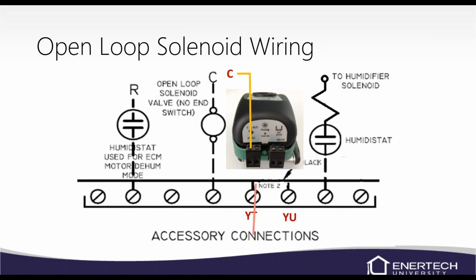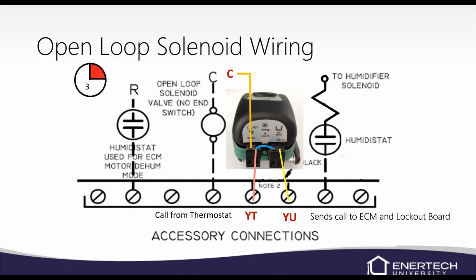Open loop solenoids, we have on our units the YT-YU connection that normally will have a jumper. If you're using one with a solenoid with an end switch, remove that jumper, run your wire up, put a little piggyback on that. So once the valve is closed, it'll send power back through and back down to your lockout board. If you're using a valve without an end switch, then you'll want to use the terminal next to it, that A connection there for an open loop solenoid, no end switch. Try to use one with an end switch if at all possible.